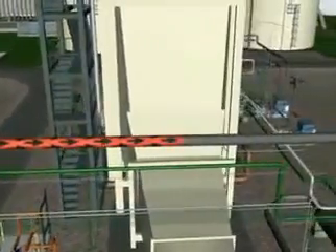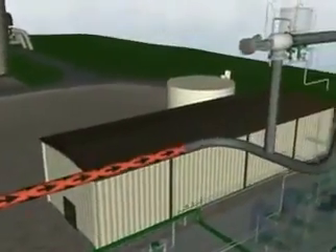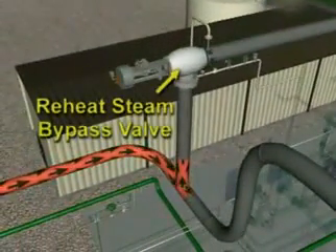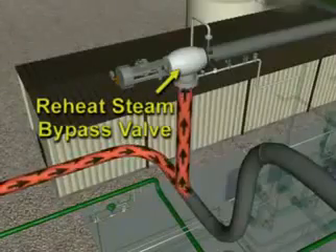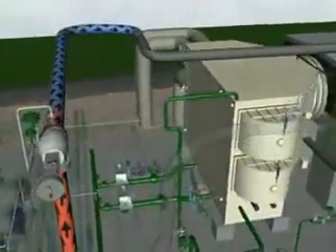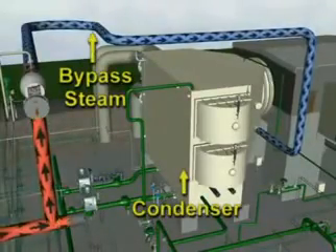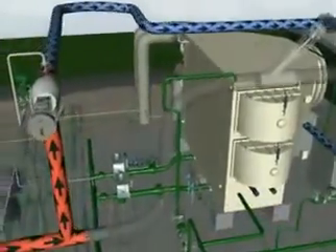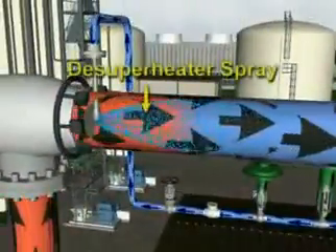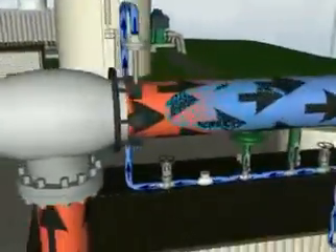Steam travels along the reheat steam line to the reheat steam bypass to condenser intersection. Under startup or trip conditions, the steam may be bypassed to the condenser by means of a bypass valve. When the hot reheat bypass line is used, hot reheat steam is bypassed directly to the condenser. Steam directed to the condenser through the bypass valve is de-superheated to acceptable pressure and temperature levels for entry into the condenser.